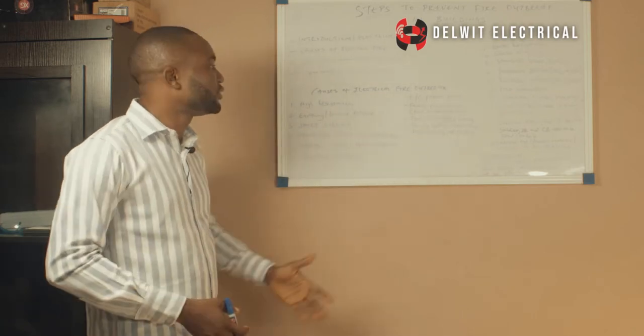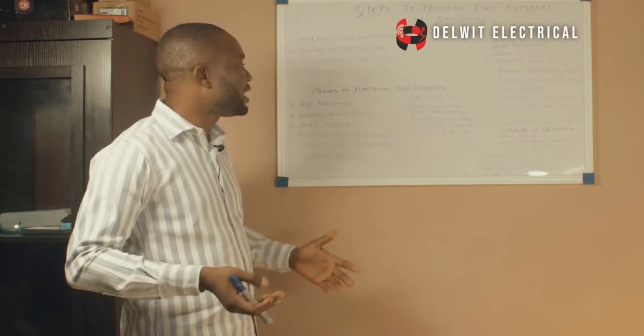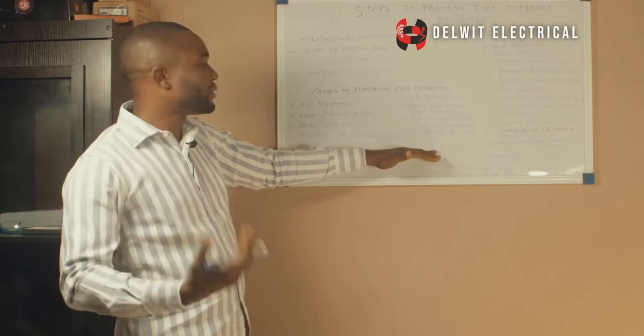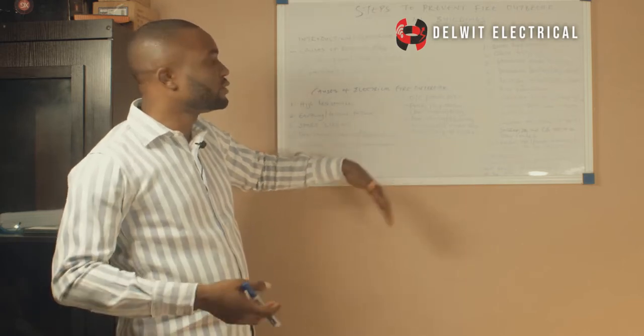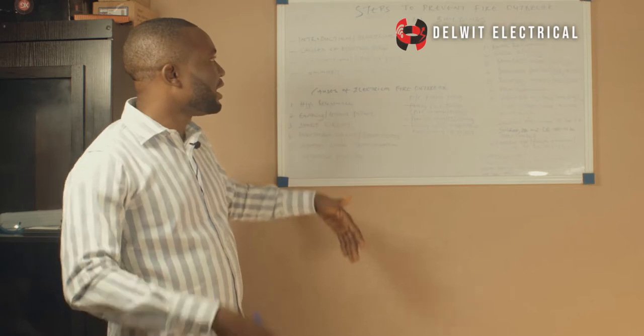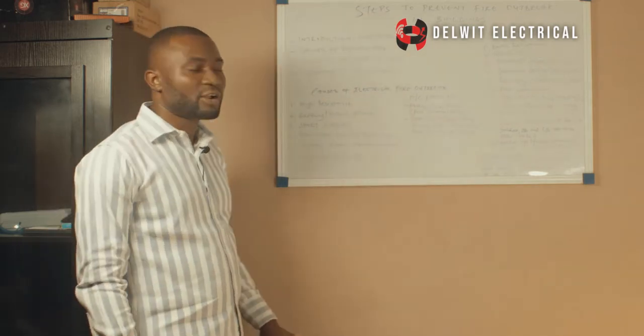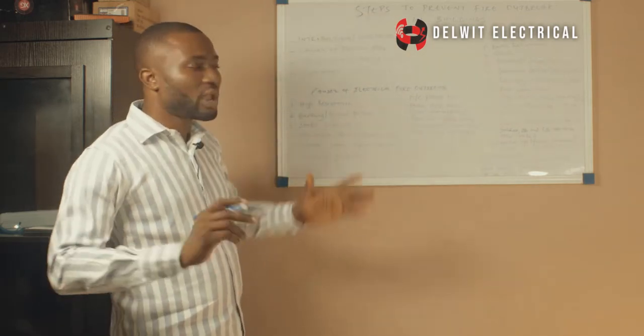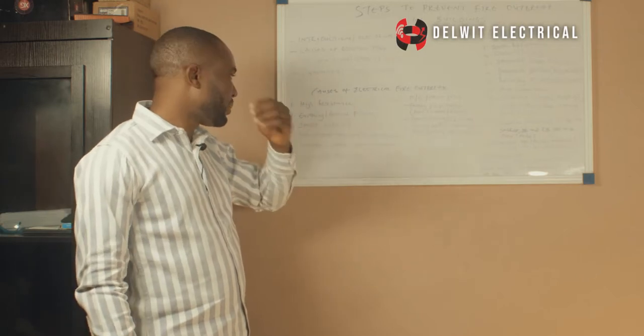But in your own generation, you are using your AC maybe 18 hours a day. And before you know it, the wire will start smelling. And if you don't take note, it will lead to high resistance, and from there you have a fire outbreak. So you must ensure that your wiring is rated to this capacity.